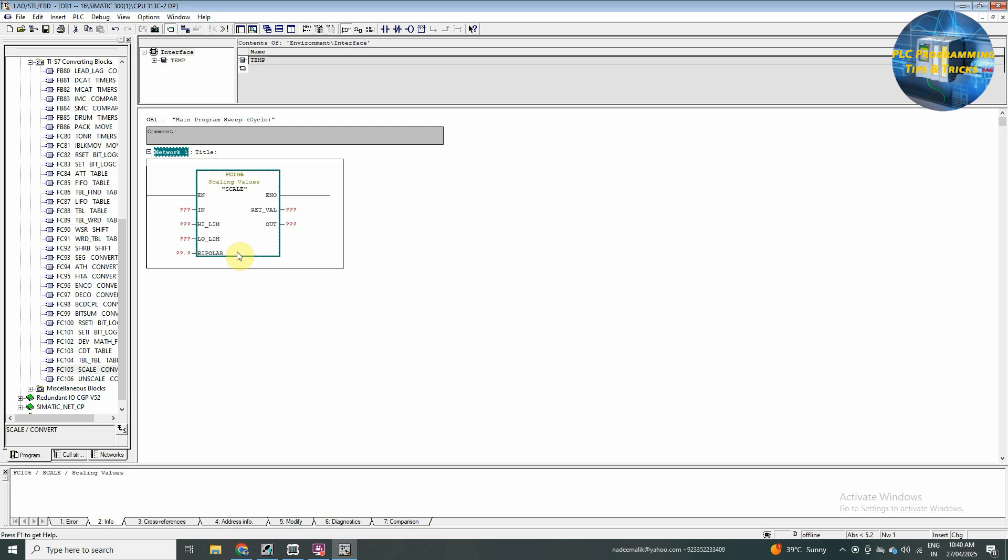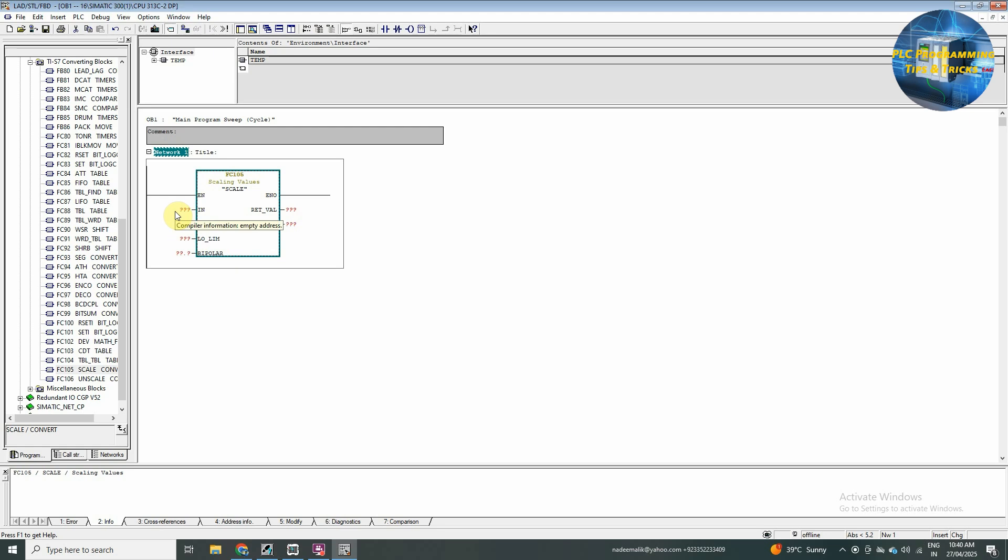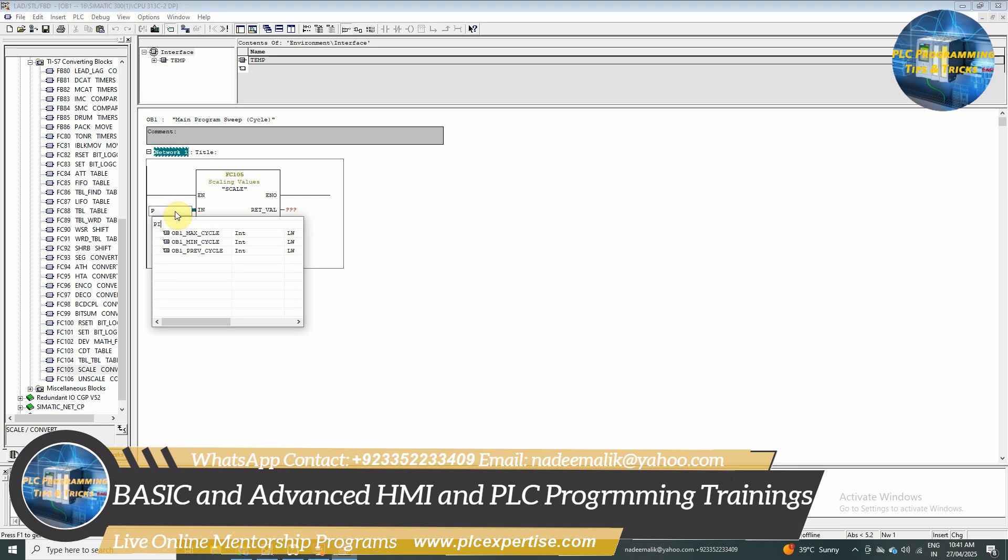And here we will use FC 105 scale. We will drag it into the network. And here we will insert the analog channel we are going to use. We will type PIW 256.